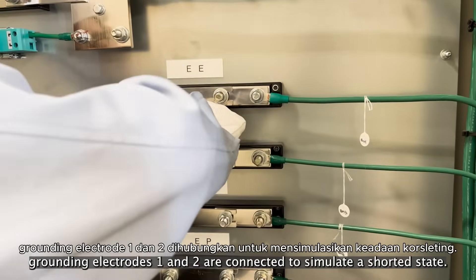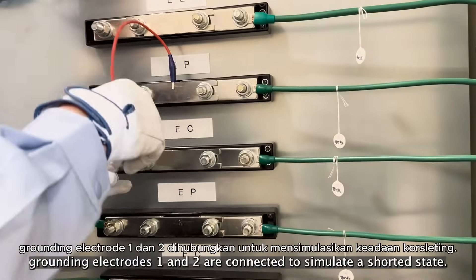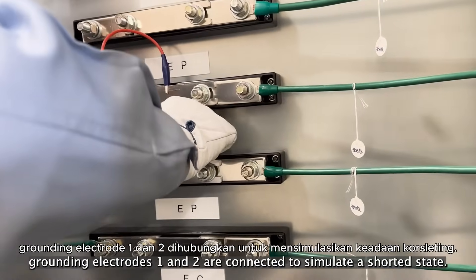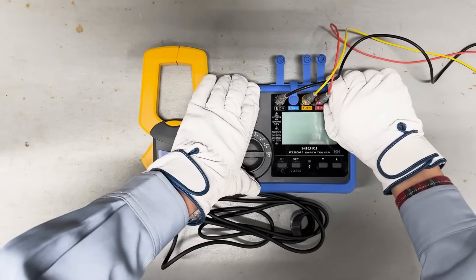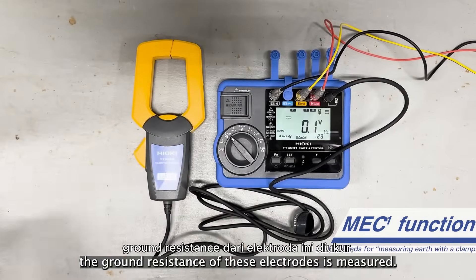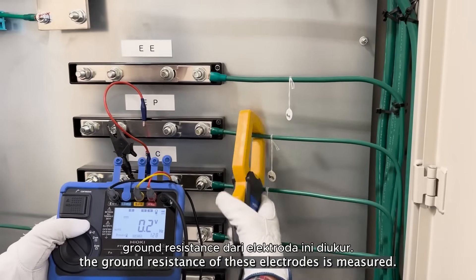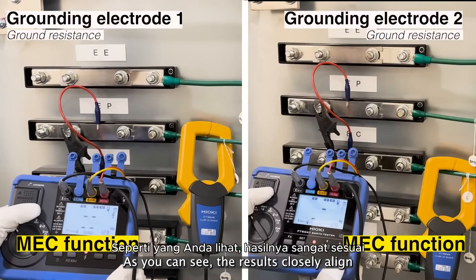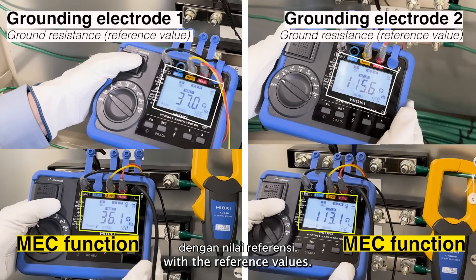Next, grounding electrodes 1 and 2 are connected to simulate a shorted state. Using the MEC function, the ground resistance of these electrodes is measured. As you can see, the results closely align with the reference values.